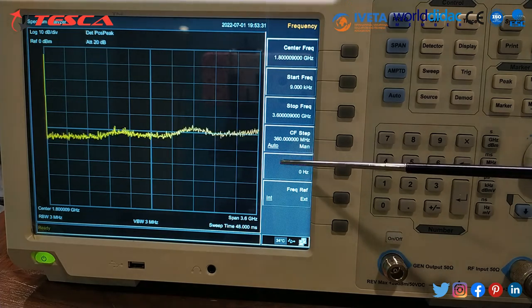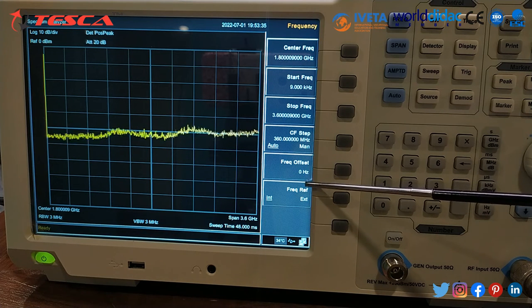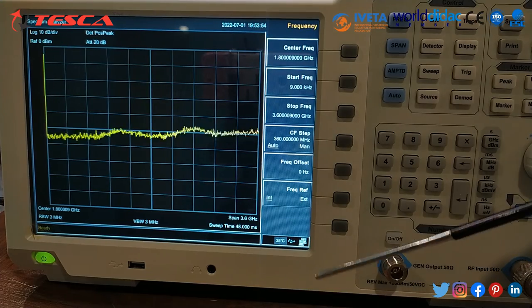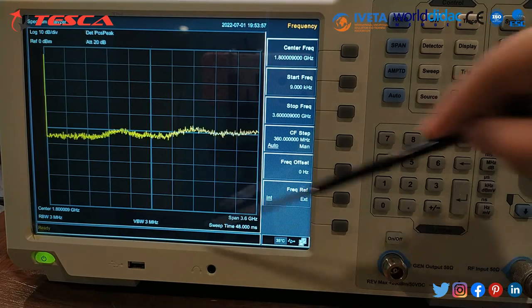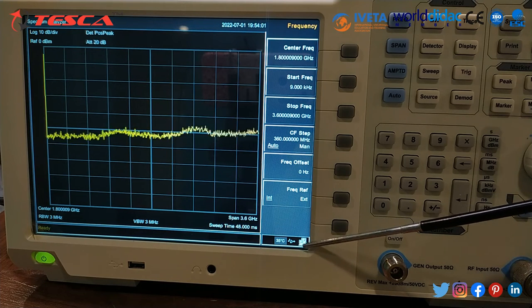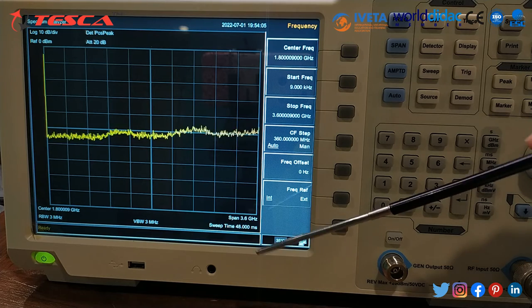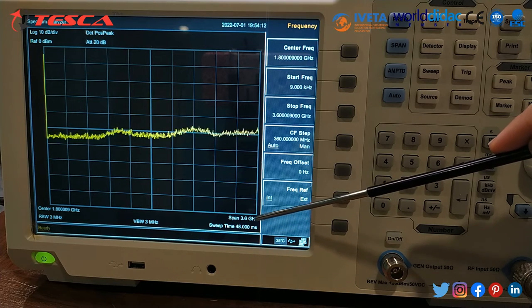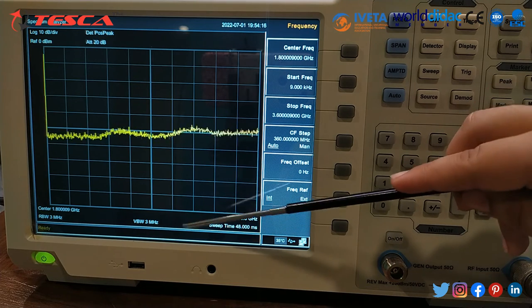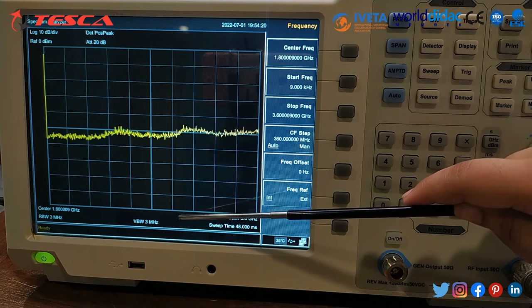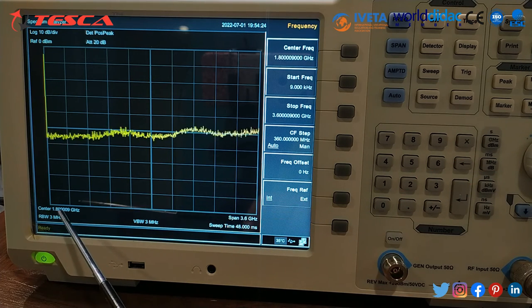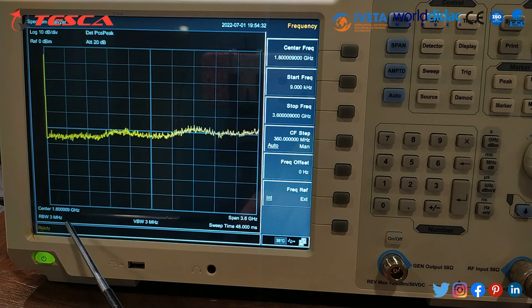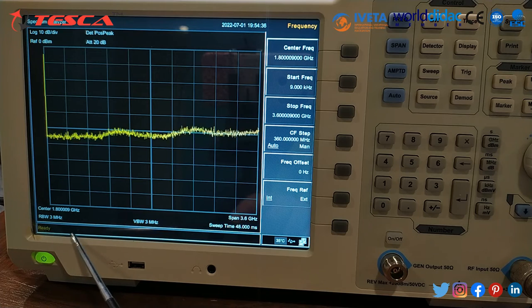The auto mode is selected. The frequency offset is 0 Hz and the frequency reference is internal. At the bottom display: LAN access sign, USB device storage, temperature sign, sweep time of 48 milliseconds, span of 3.6 GHz, VBW (video bandwidth) of 3 MHz, center frequency of 1.8 GHz, resolution bandwidth of 3 MHz, and the system status shows the system is ready.